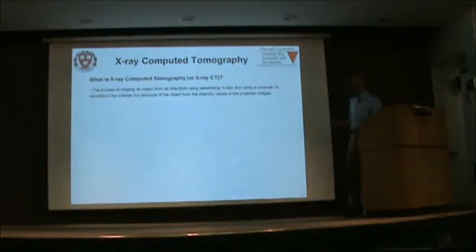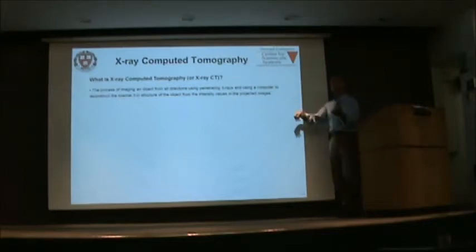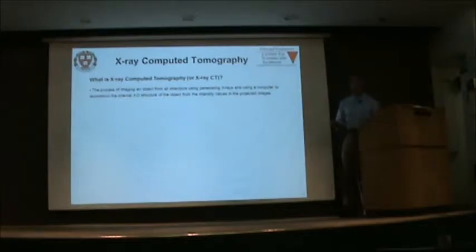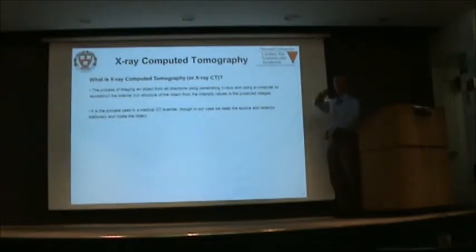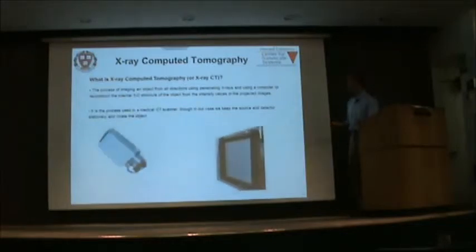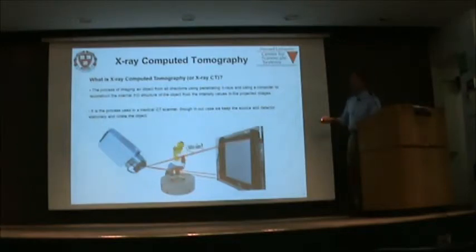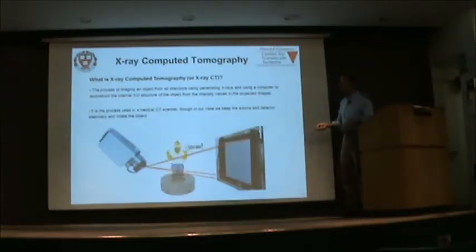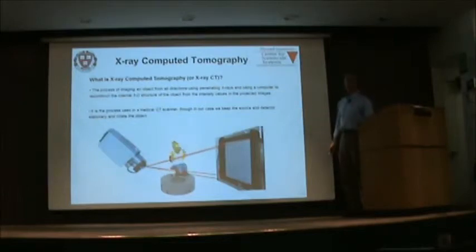That's what X-ray micro-computed tomography, or MicroCT, is: the process of imaging an object from all possible directions, rotating it 360 degrees while taking projection images, then using a computer to reconstruct the internal structure. In medical CT scanners the patient lies still and the detector and source rotate around the person. We don't have that restriction, so we simply rotate the sample — which is more robust because the source and detector are on a very stable frame, and the sample has far less mass to control.